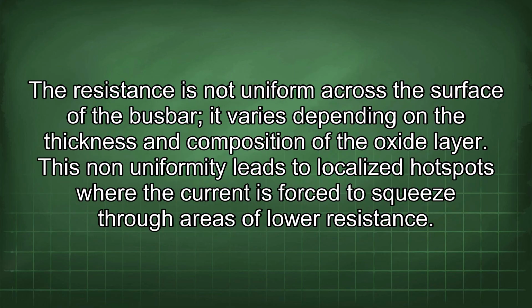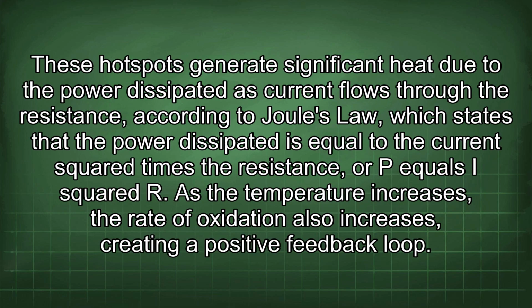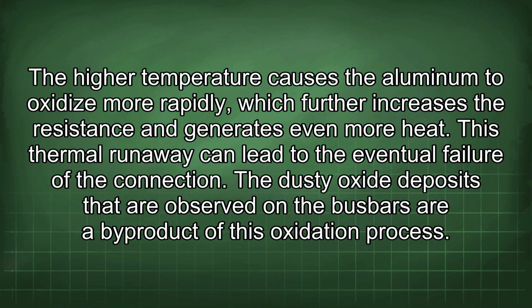The resistance is not uniform across the surface of the busbar. It varies depending on the thickness and composition of the oxide layer. This non-uniformity leads to localized hotspots where the current is forced to squeeze through areas of lower resistance. These hotspots generate significant heat due to the power dissipated as current flows through the resistance according to Joule's law, which states that the power dissipated is equal to the current squared times the resistance, or P equals I squared R. As the temperature increases, the rate of oxidation also increases, creating a positive feedback loop. The higher temperature causes the aluminum to oxidize more rapidly, which further increases the resistance and generates even more heat. This thermal runaway can lead to the eventual failure of the connection.